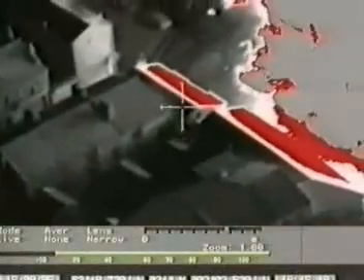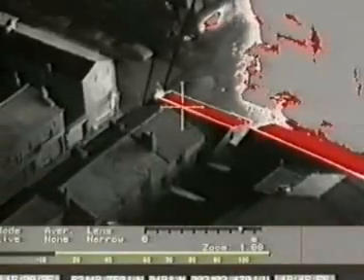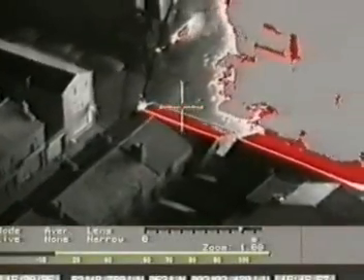Again, in infrared, we see the roof opposite the fire source as red. This shows the temperature of this roof slope due to the radiant heat from the fire. This is why Building Regulation Approved Document B requirement states the roof of the building shall resist the spread of fire over the roof and from one building to another, having regard to the use and position of the building. This applies to roofs, the roof covering material, and parts of roofs — which would include accessories such as tile and slate ventilators.